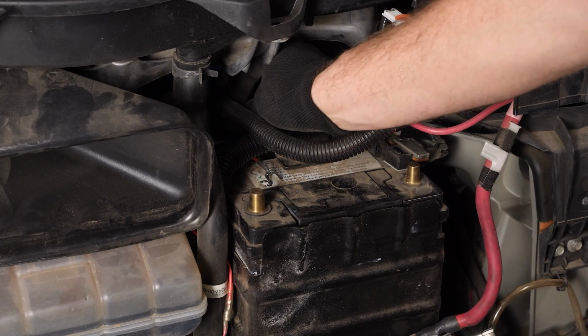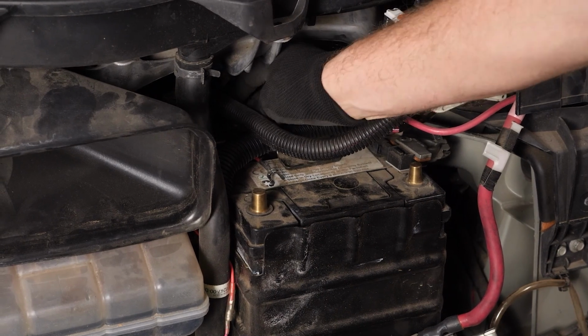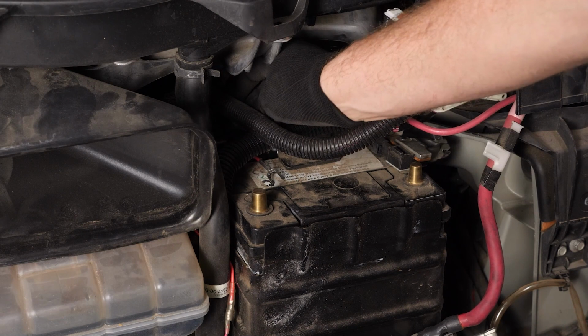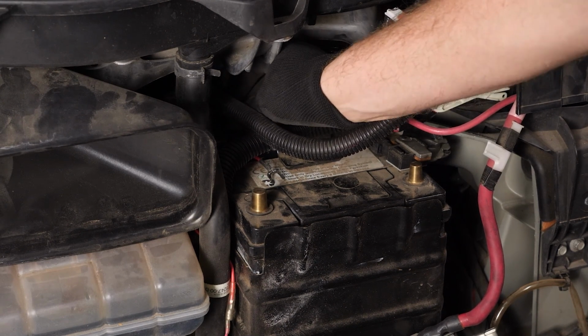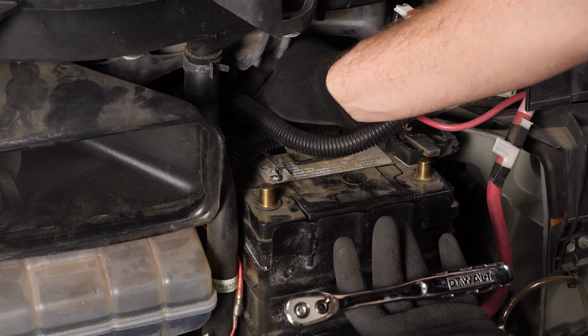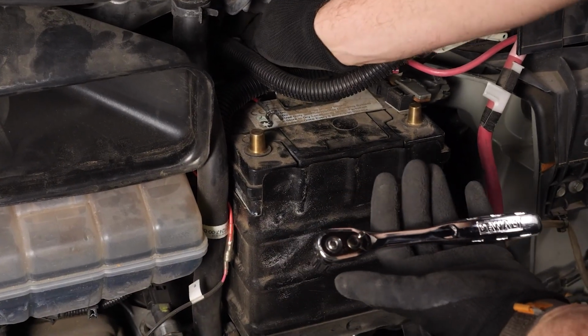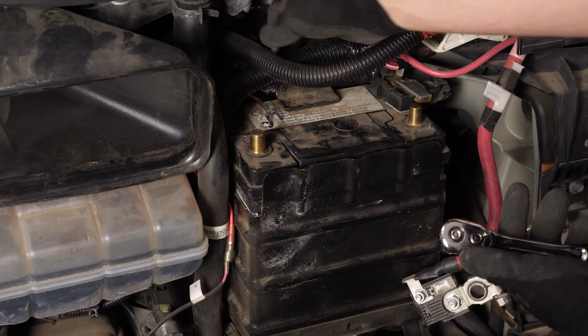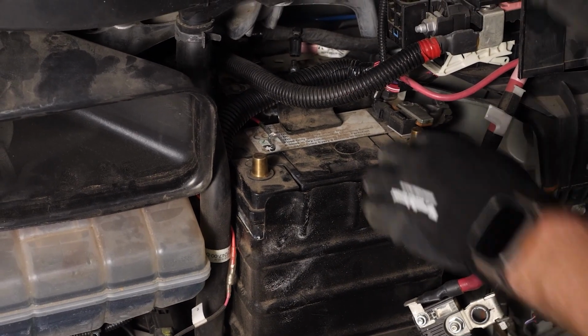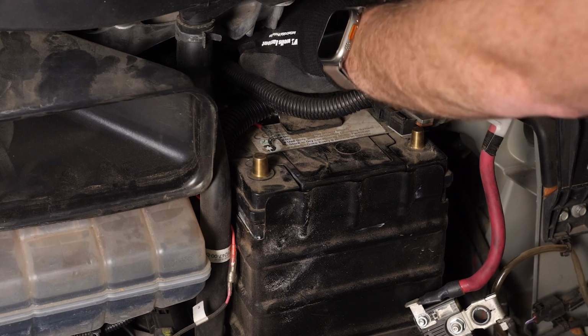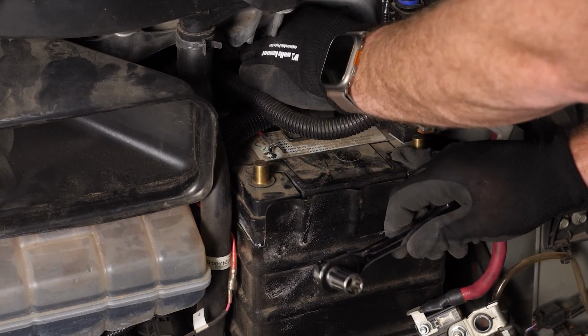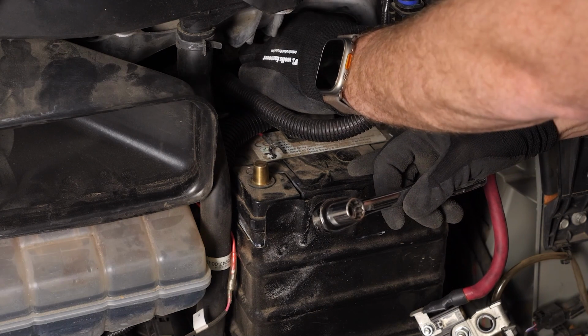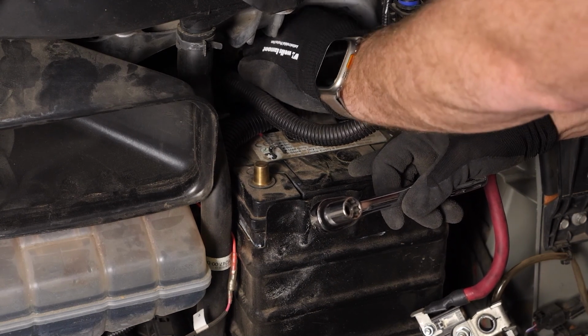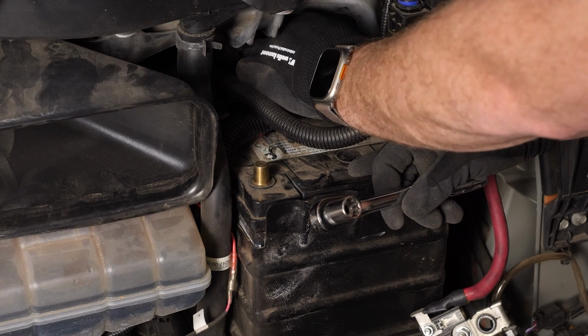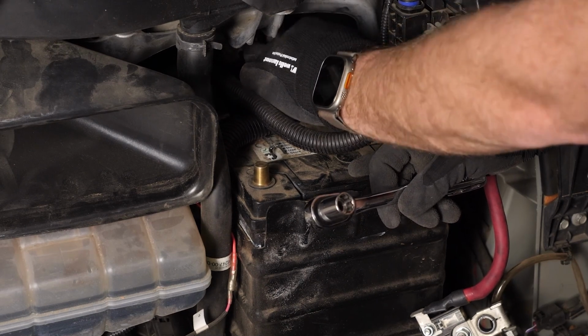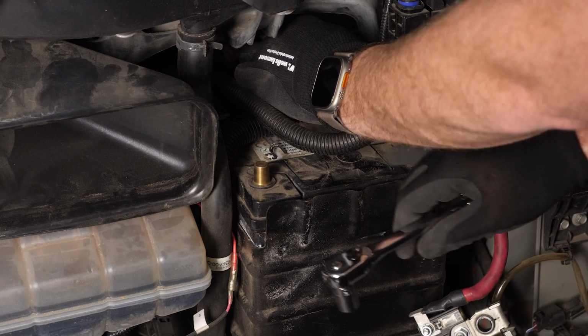While you're in this area, this is one of the big reasons we make sure we wear rubber gloves. This tool is actually an example of a very bad tool to use because it's not insulated at all, but it's a really good idea to have an insulated set of tools when working with live voltages. If you were to drop this socket wrench across your terminals on this battery, it actually has built-in protections and safety, so it wouldn't do much - but if it were a lead acid battery, they have no internal protection whatsoever, and it would immediately start dumping all its energy through the short circuit you've created.